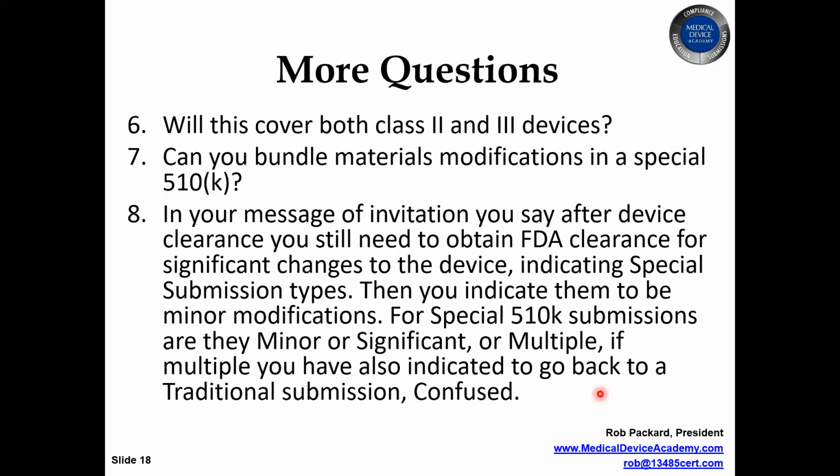Next question. In your message of invitation, you say, okay, so I'm not going to read this whole thing. Everybody can read, but I think what happened here is that in my message of invitation that I sent, I had a typo, and I didn't make some things clear. So special 510Ks are only for minor modifications, not for significant changes. You could use it for multiple modifications, but they'd have to be very minor, and they would all have to be in the same functional area of review by the FDA. So yes, multiple, no significant, yes, minor. And the multiple, even though it's a yes, has that caveat, they have to be in a single area.